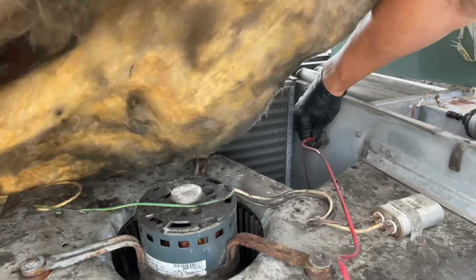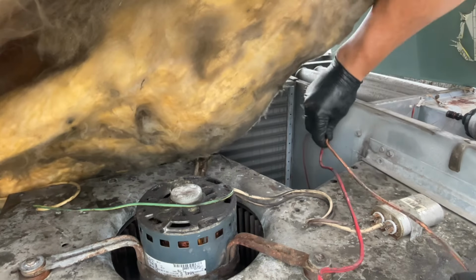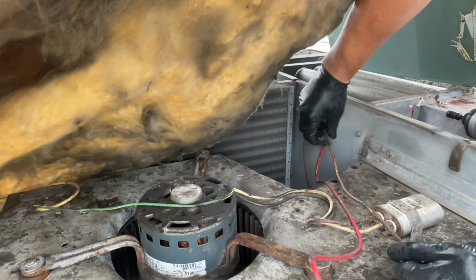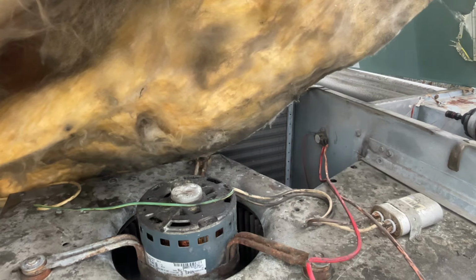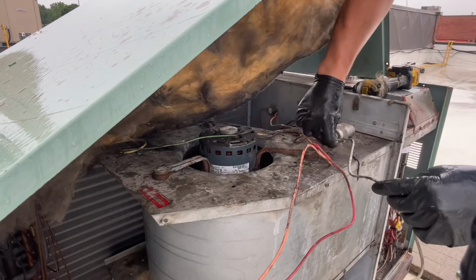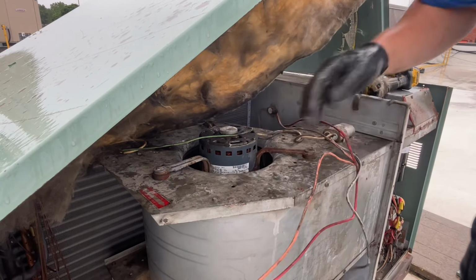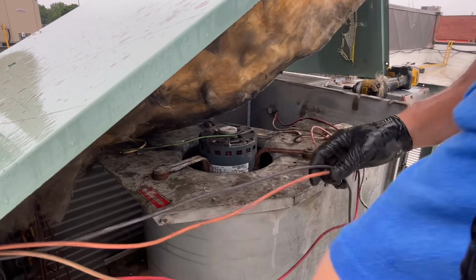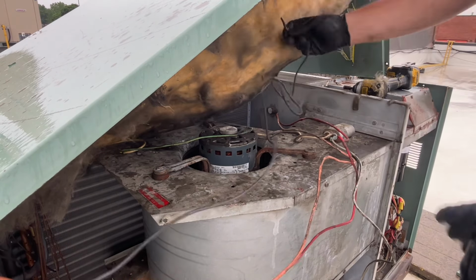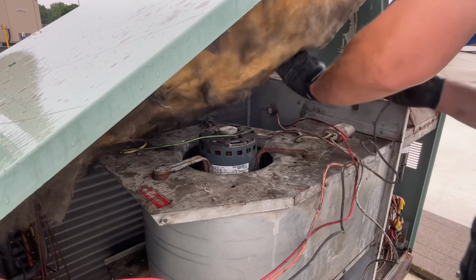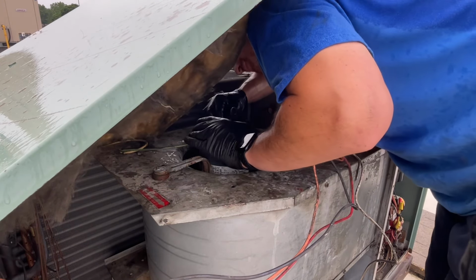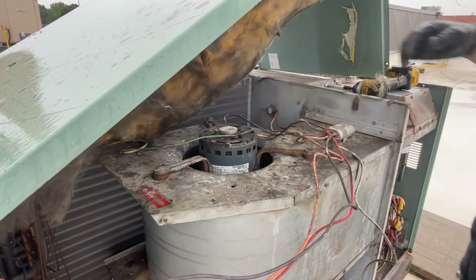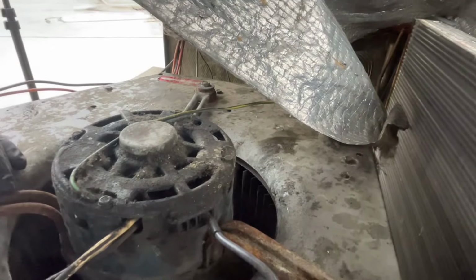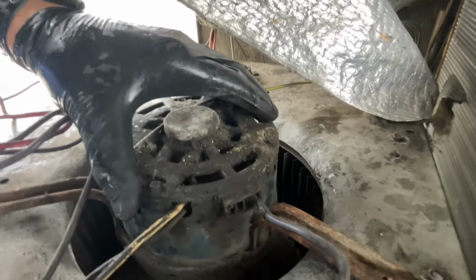Now we're gonna hook back up our high limit wires, 1, 2. Put in our common for our cap. And then we got power for our motor, which is here. This is a multi-tap motor, so it's multi-speed. We're gonna put this one on the highest speed, right in the back there. Show you guys quickly, those are our speed taps in the back here. We put it on the highest speed.